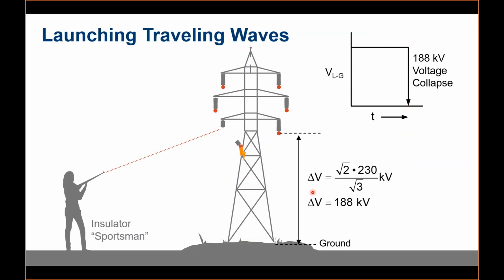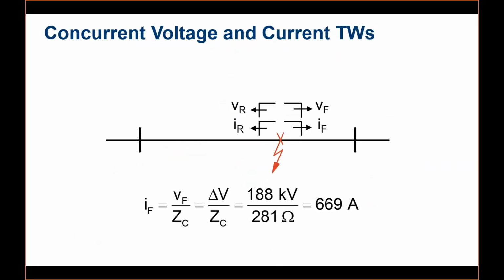We have a relationship to find the change in the voltage if it is a 230 kV line, assuming the fault happened at the peak of one of the phase voltages. The change can be estimated as 188 kV. Conceptually, whenever there is a fault, a traveling wave originates from the point of fault and travels, same as in the case of water, in both directions. Water is 360 degrees, but in the line you have only two directions: the reverse side or the forward side. So whenever there is a disturbance, or a change in the voltage, it travels from the point of fault in both directions. So this is how it travels.